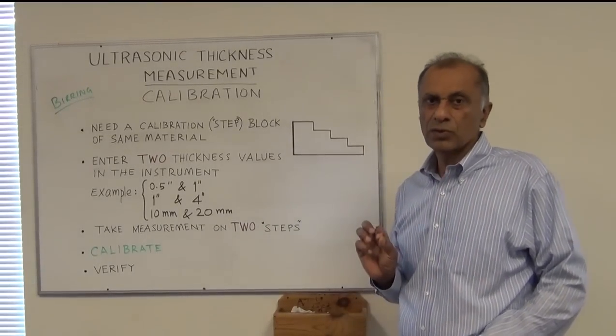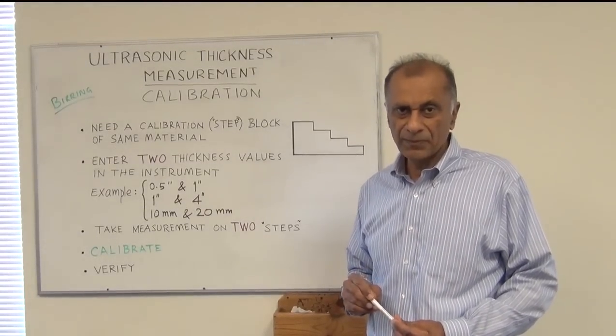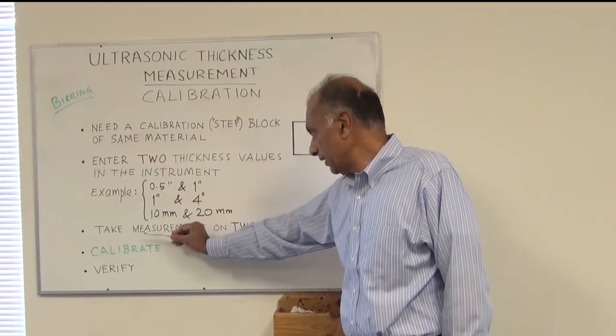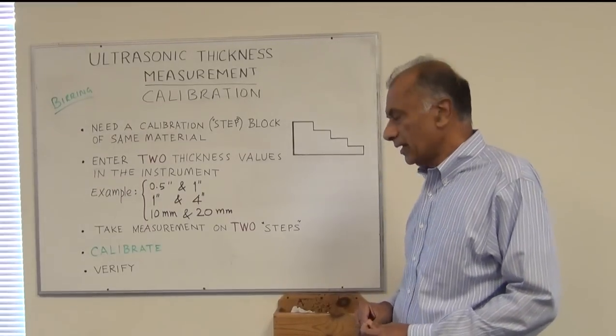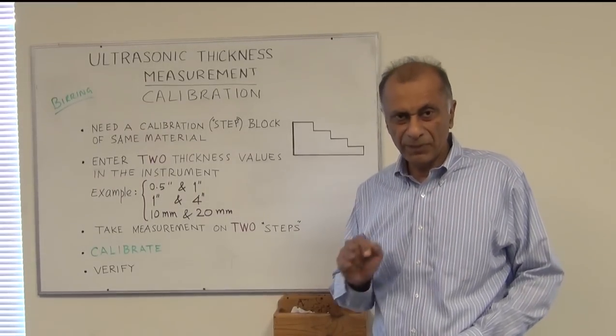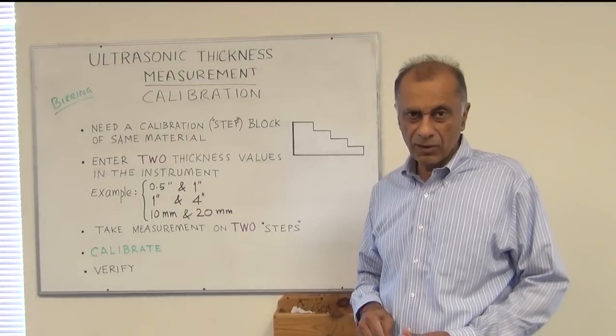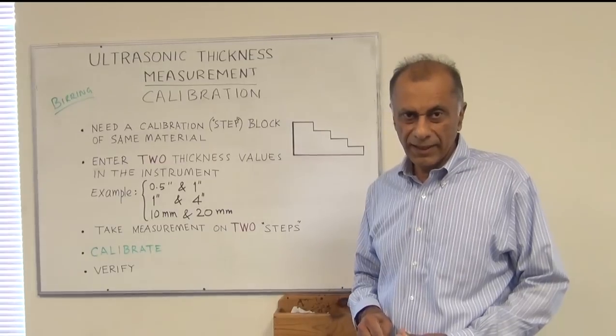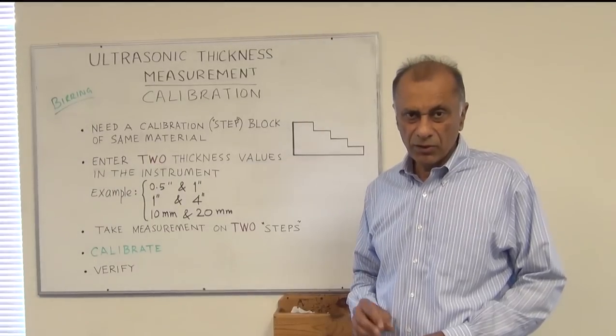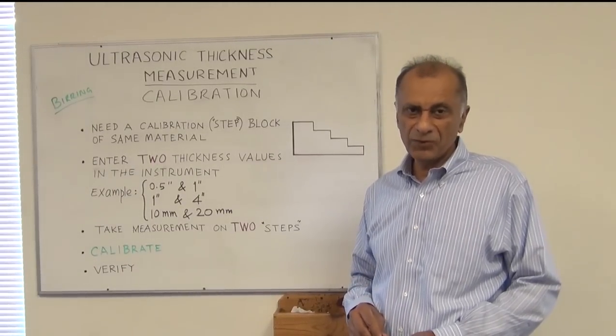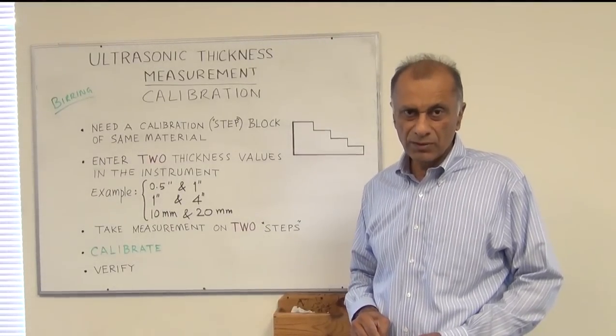We take those two selected numbers and enter them into the machine, and then after that we take the measurements on those two selected steps. Then we calibrate the machine, and by doing that the machine automatically calculates the velocity and the delay on the machine and the machine is calibrated. Once the machine is calibrated, in order to be sure that the calibration is correct we have to verify the calibration back on the step block with known thickness steps.